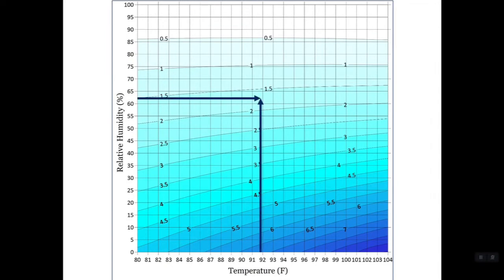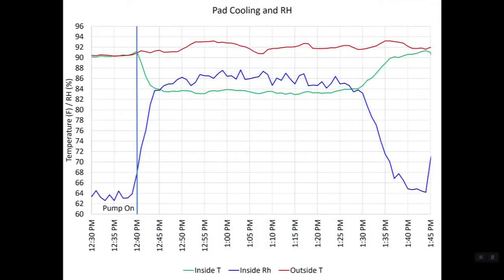What about water usage? Again we draw a line up from 92 degrees over from 62 percent humidity. We come up with the water usage per 100,000 CFM should be about 1.75 gallons per minute. The house happened to have 300,000 CFM operating with all of its fans running. We multiply 3 — that's 300,000 — times 1.75, and the chart predicts that the pads would be using about 5.25 gallons per minute.